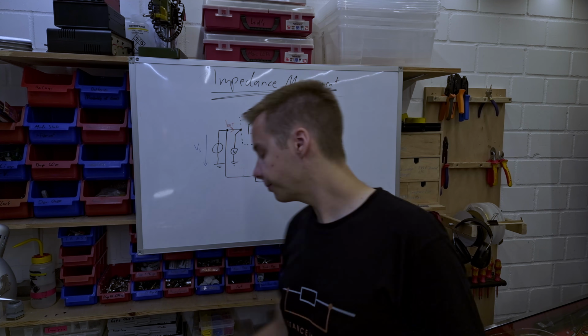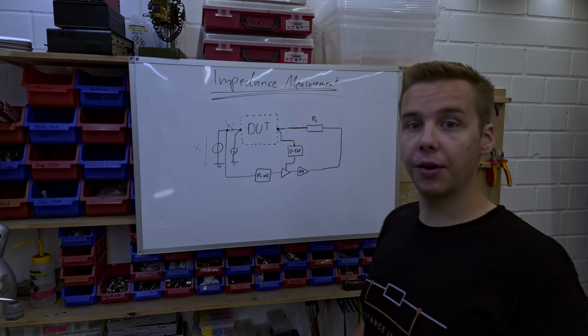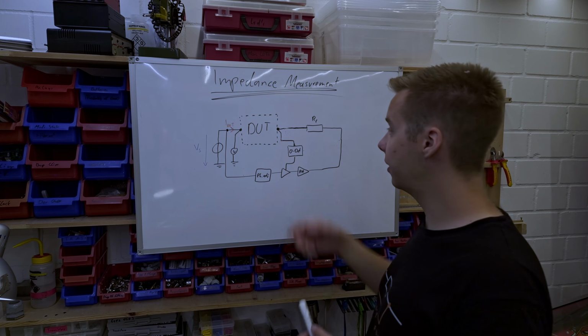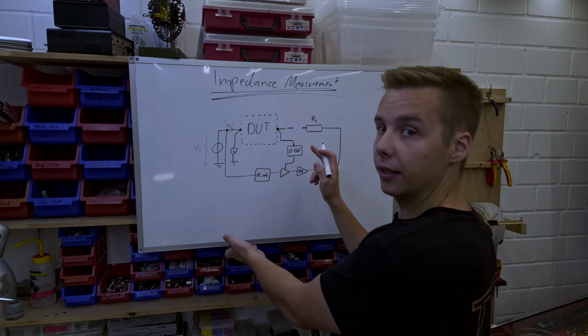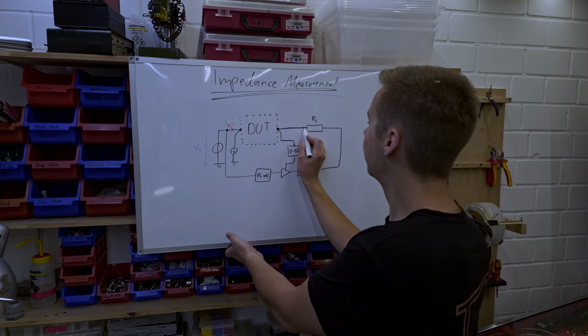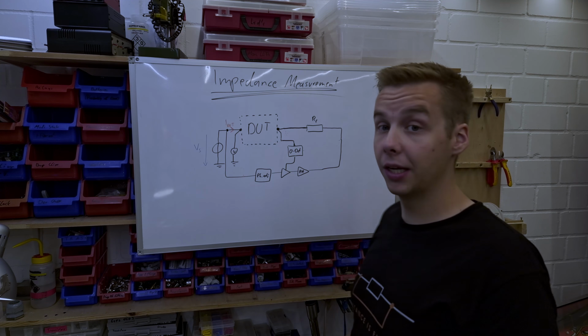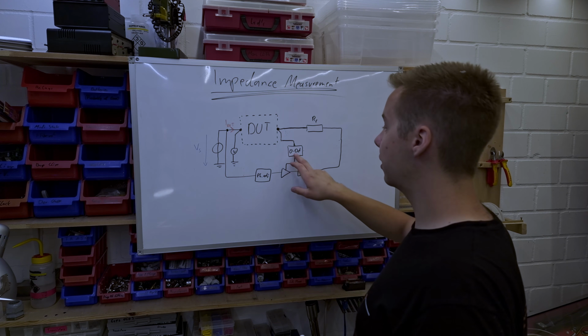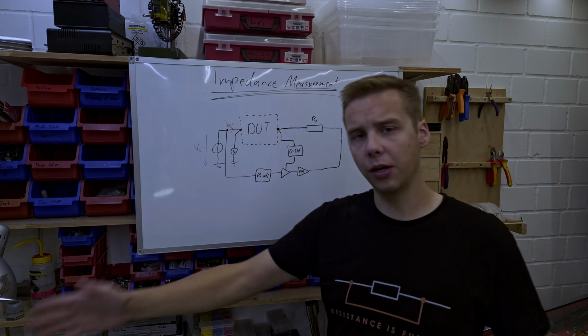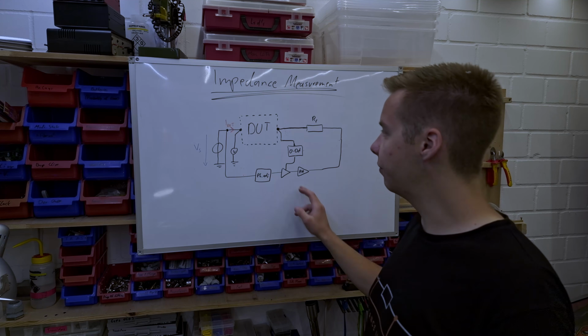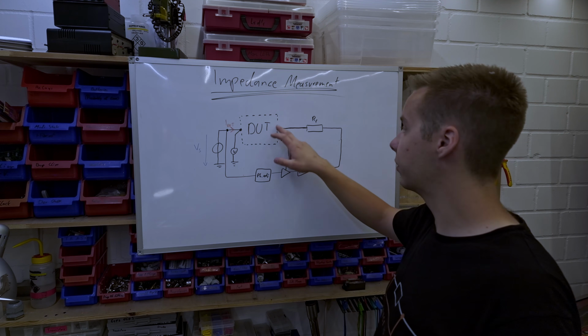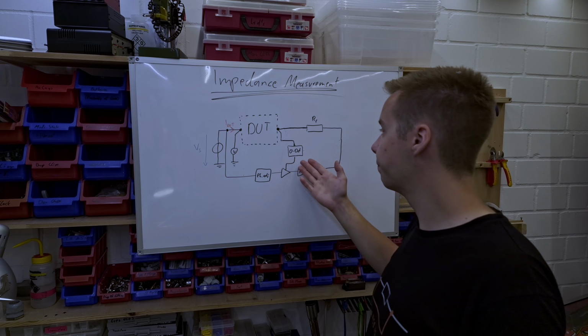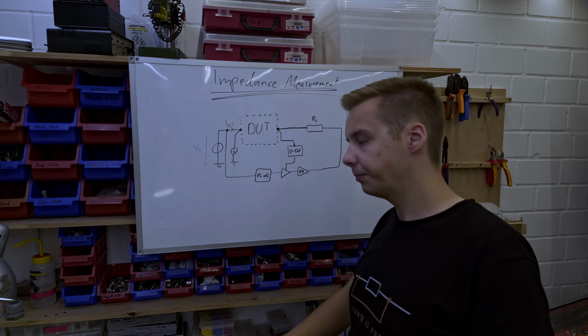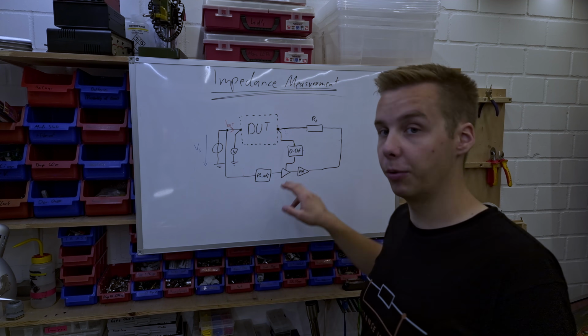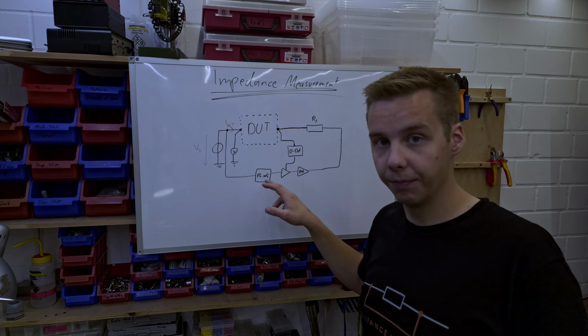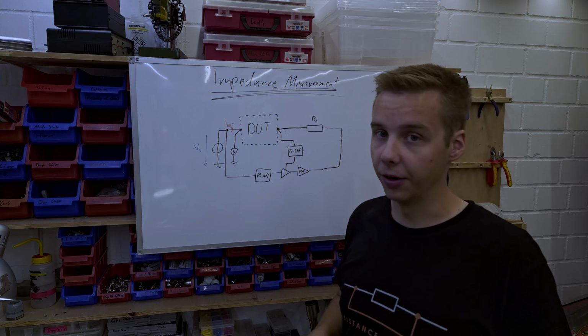What I was just saying is what could that bridge unbalance error be caused by? Well, we've already seen if this part of the wire here is open, it would be unable to balance the bridge. But of course also a fault in the null detector could result in this. So if this thing always told the amplifier, hey, go full on, give all you can, even if there was basically no current flowing through here, then you would have a voltage at this point. Or if that thing always said, hey, slow down, we're already way off, don't output anything, even when there was a voltage here, it would of course also result in a bridge unbalanced error.